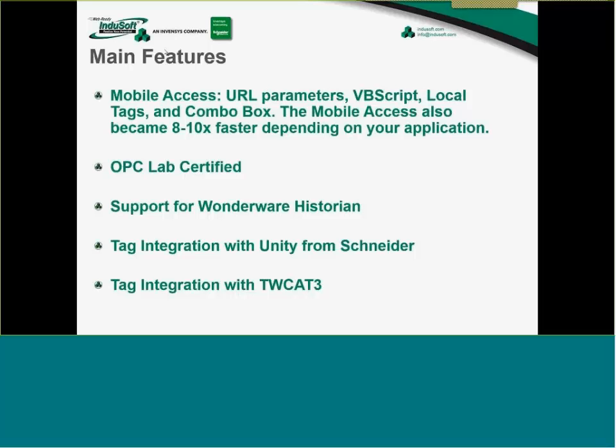And I strongly recommend that you look into that so you don't have to create your tags twice. For those of you unfamiliar with tag integration, it means that you can create your tags in your PLC programming software and use those tags inside InduSoft Web Studio, so you don't have to recreate them or configure communication to use them. And we brought these concepts for the UnityPro with the Schneider PLCs.